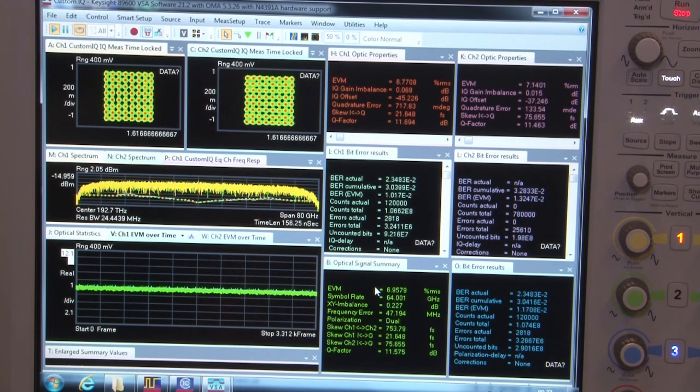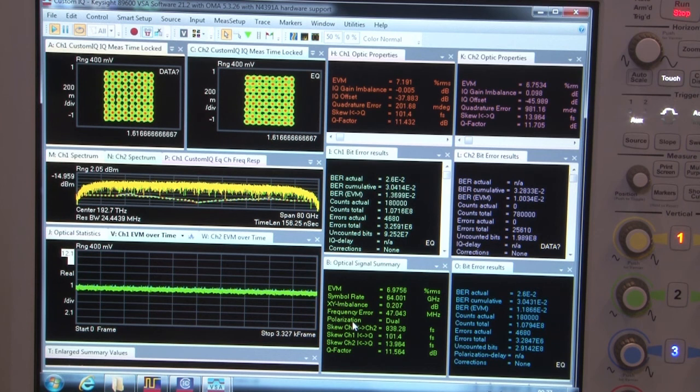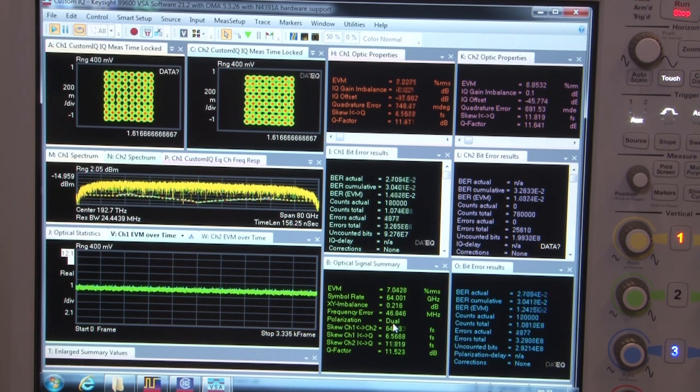On the left-hand side finally we have a screen that's called the optical signal summary. Pretty much similar to the statistics but without the statistical representation. So again we see the symbol rate, EVM, XY imbalance, frequency error. The polarization type is reported down here. So we see if it is a dual polarization or single polarization signal. And again the set of skews is reported down here.